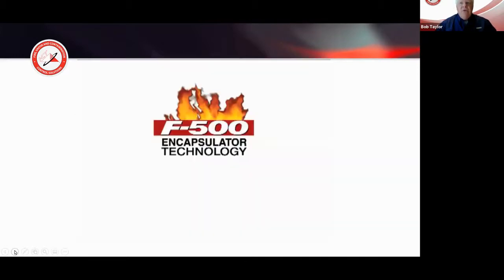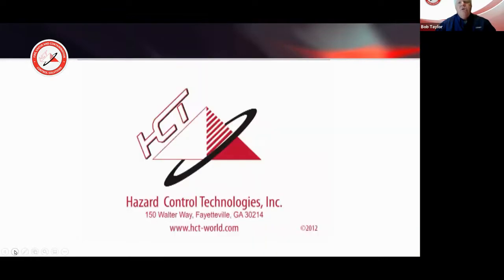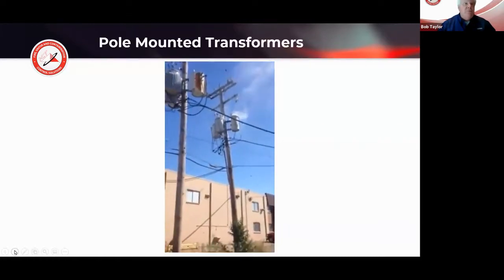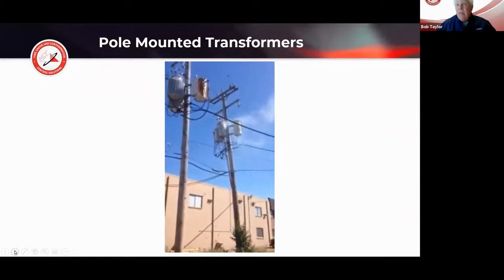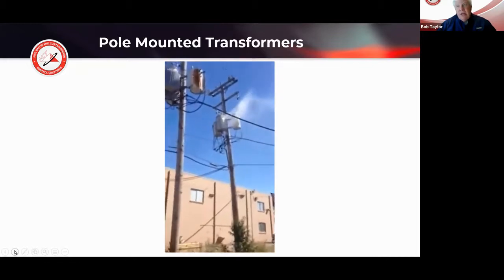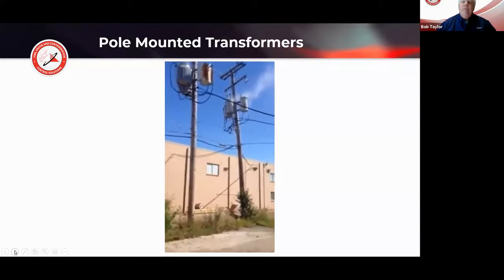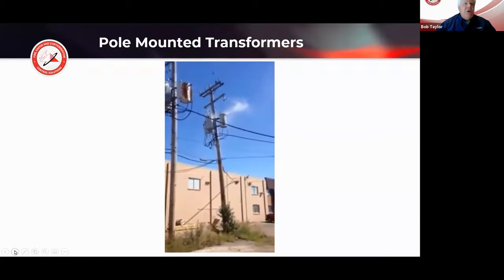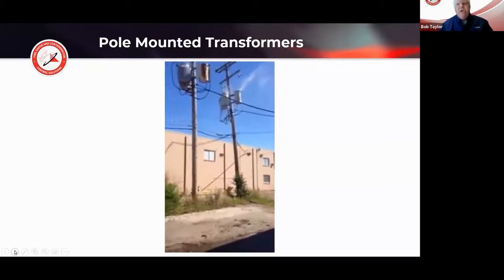When these fires erupt, and they are likely to erupt, the use of firefighting foam is generally not effective, whereas F500 encapsulating agent has a proven history of being very effective, both in cooling and in encapsulating, reducing the toxics and smoke, and the water runoff is biodegradable and not an environmental hazard the way foams and other agents present. We're beginning to see more and more application on transformers because it works on all levels, including Class B fires, elevated fires, in any community today, and it works effectively on the wood pole and the vegetation around it, covering all the bases with the least amount of agent.